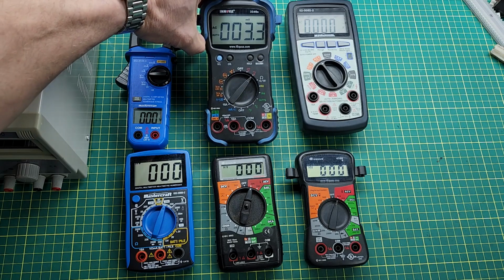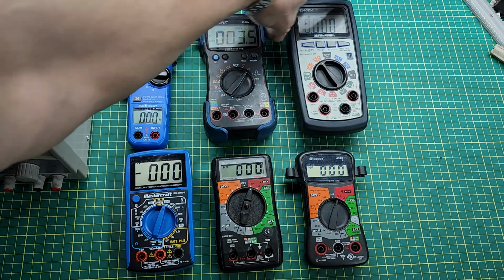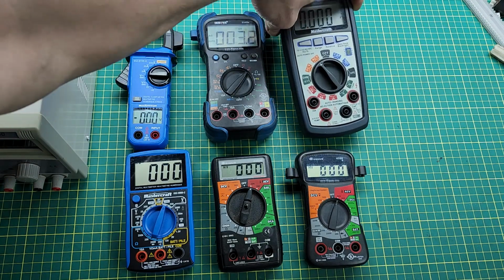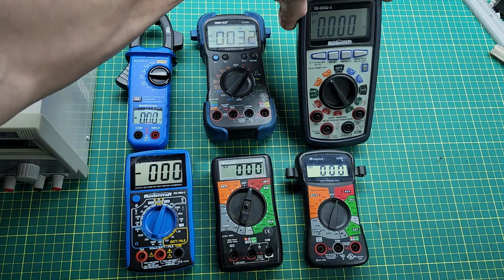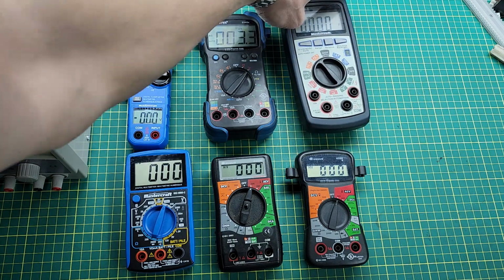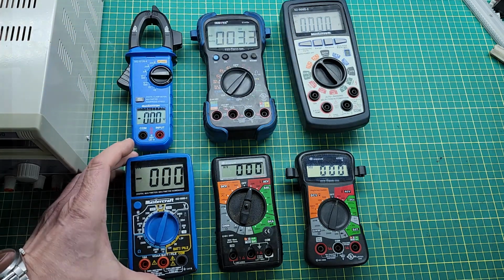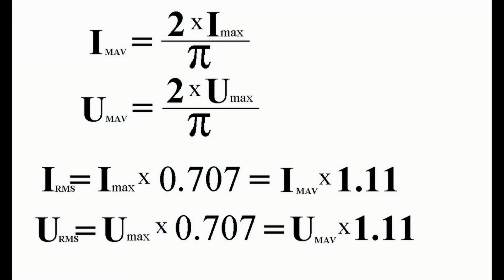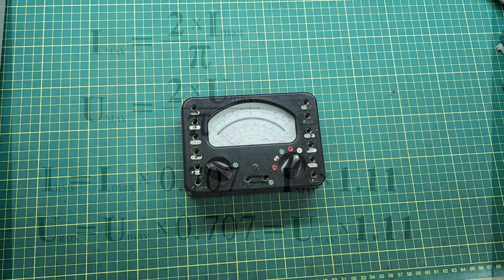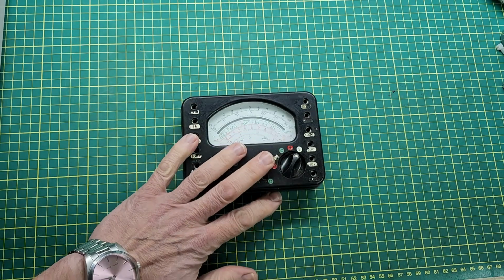Multimeters that are not true RMS meters measure a mean of the absolute value, in other words, an average rectified value. Assume they measure sinusoidal current or voltage when set on the AC function selector, and using their internal algorithm, multiply this value by 1.11. Obviously, we are talking about digital meters here.